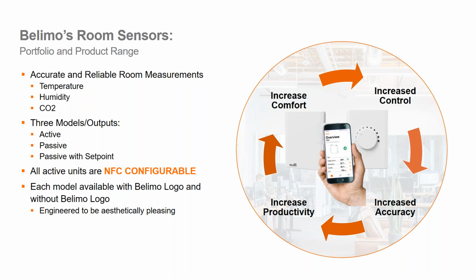We have models with active outputs, your standard passive output model, standard 10K type 2, 10K type 3, 20K NTC, and also a passive model with standard passive sensors with a set point dial or set point adjustments. With our active units, they can all be configured via NFC and the Belimo Assistant. So if you have not seen this, Belimo offers a download for both iPhone and Android that communicates with our NFC capable devices. All the active wall mount sensors that Belimo makes have NFC in them. And so you can simply open up the Belimo Assistant, put it next to the sensor. It's going to find the sensor. It's going to open up the sensor's parameters. You can adjust the active outputs and the measured values and things like that.